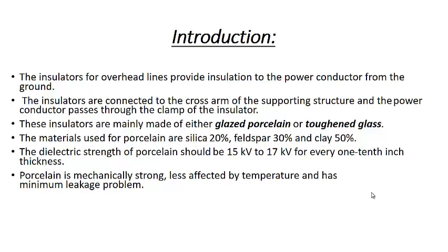equipments, we can say they are usually the equipments that provide the insulation to the power conductor from the ground. The insulators usually are connected to the cross arm of the supporting structure and the power conductor, which passes through the clamp of the insulator. Usually, power conductor passes through the upper part of the insulator.